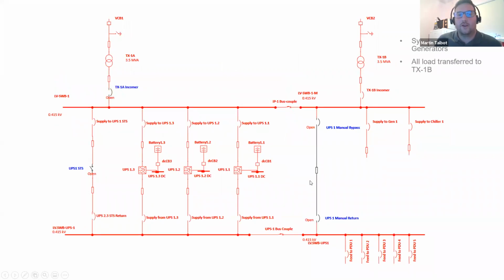So when we're going to do this, we're going to transfer all of our load from TX1A to TX1B to begin with, to get our UPS into being supplied by one system. We're also going to transfer our system to generators. So it's important to know, how is our protection system set up? Does that make any changes in respect to the arc flash considerations that we've got? The generators provide more or less incident energy.